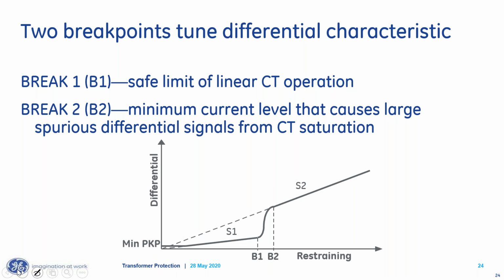I might have set the transformer for the nominal tap, but I might have it at a higher or lower tap if it's got a tap changer. And unless I'm going to change my settings every time I change the tap, that's going to cause me problems. So typically on a transformer, that lower slope, I would say set that for 30% or 35%.